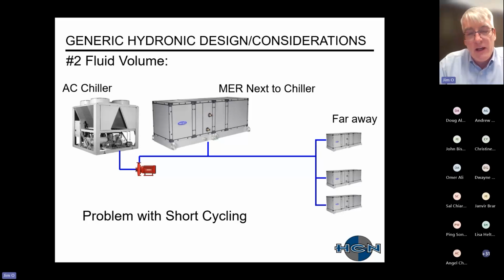But in actuality, what ended up happening is that those other smaller units were offices and they were intermittent. And the large air handler that was right next to the chiller ended up being a hog and using all the chilled water that was in the chiller. So we ended up with a problem of short cycling the chiller. So we ended up having to add a volume storage tank on the chiller there.